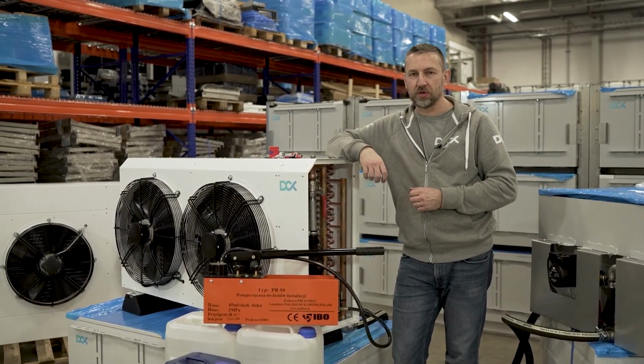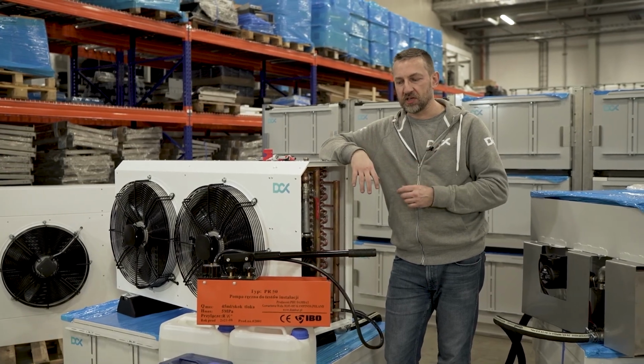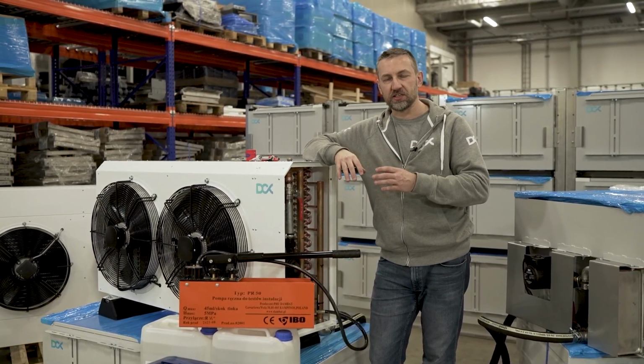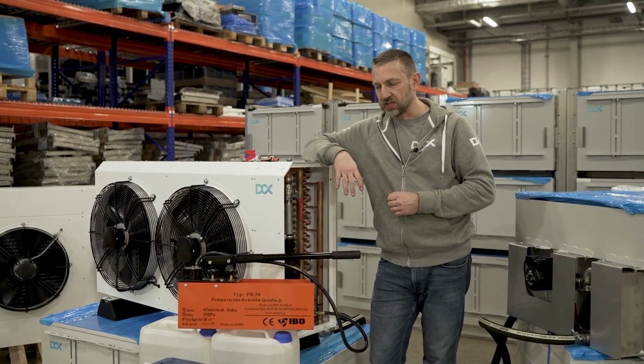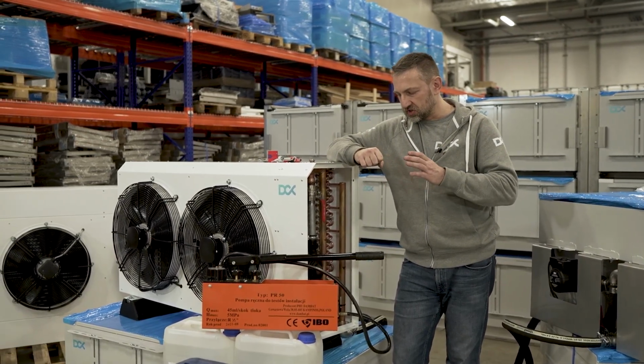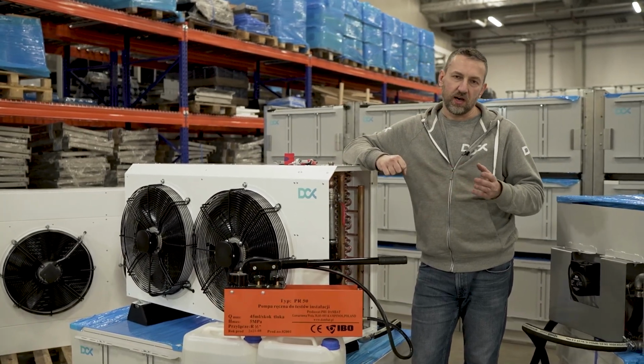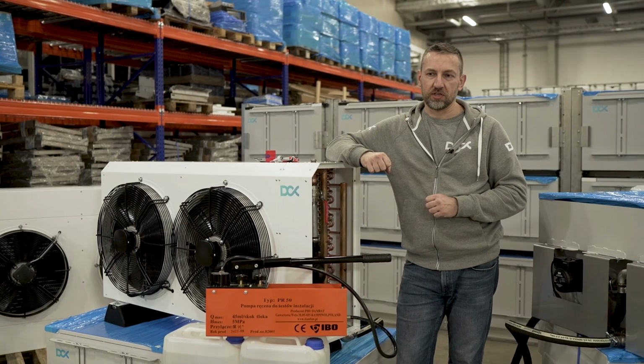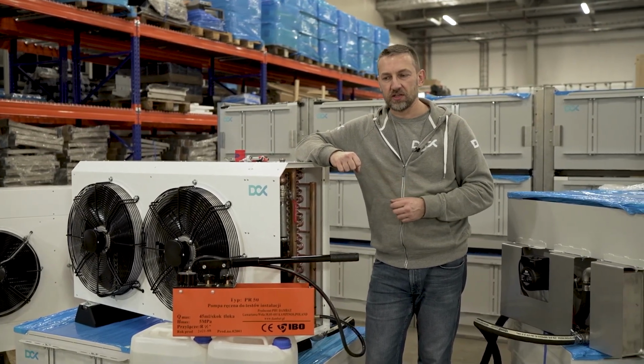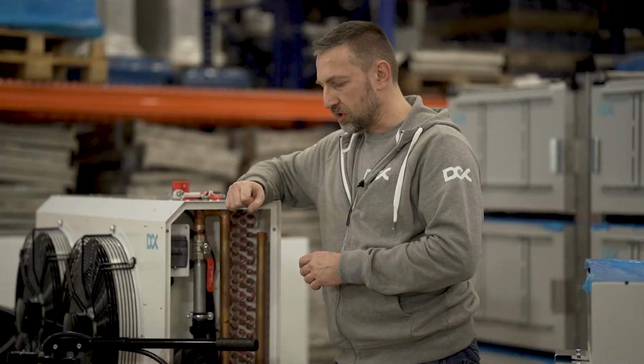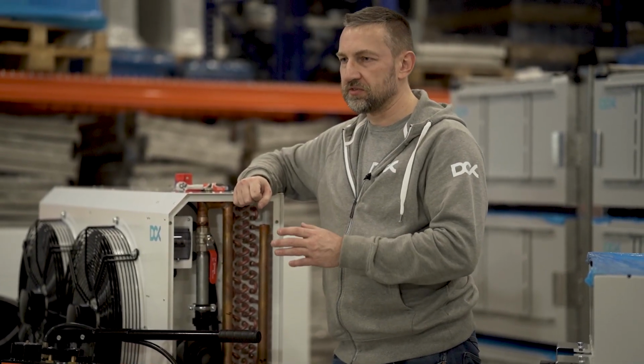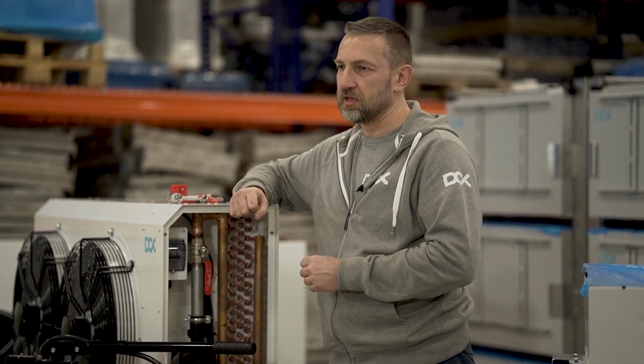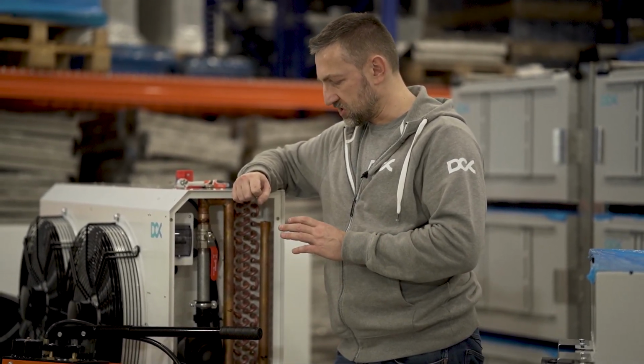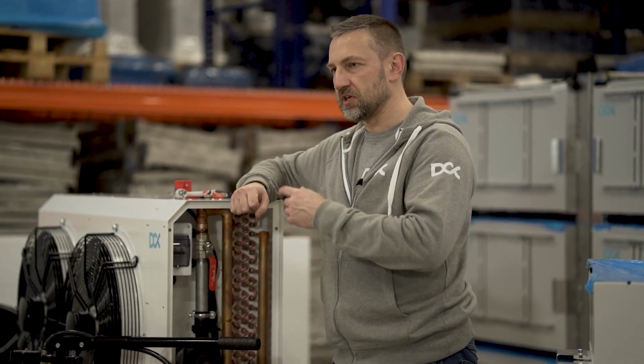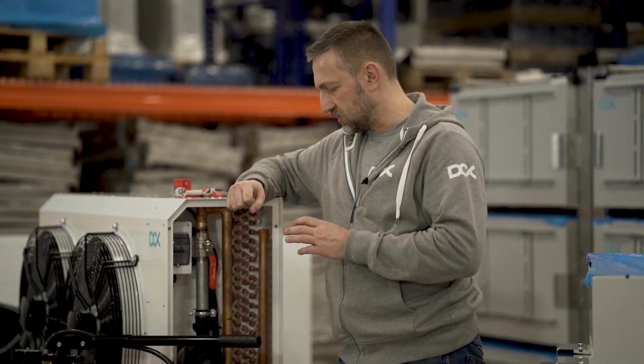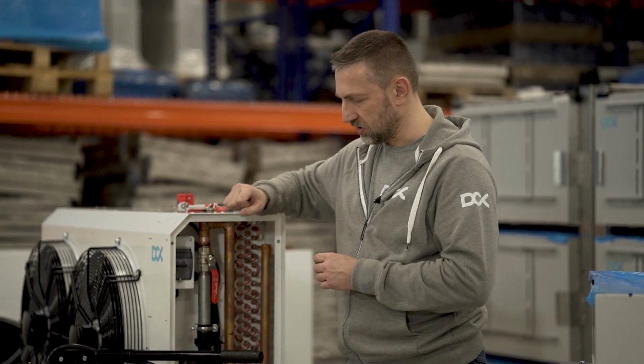And if you observe the manuals on our website, you will see that, for example, 50% glycol will protect you down to a certain temperature. You will see that table in the manual on our website. Just buy the antifreeze mix locally. You can use antifreeze mix for car radiators, so winter antifreeze car radiator fluid will be just fine. You can use demineralized water mixed 50-50 with propylene glycol or ethylene glycol, but they're both just fine. Just make sure you are properly protected. Observe the manual on our website, and do not ruin your dry cooler during the colder season.